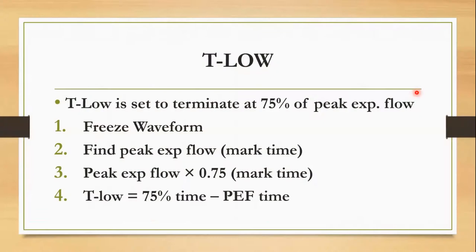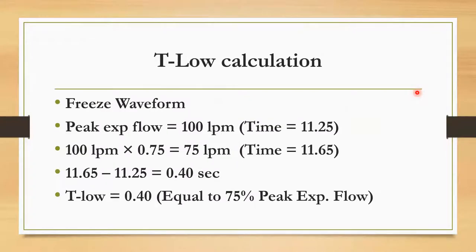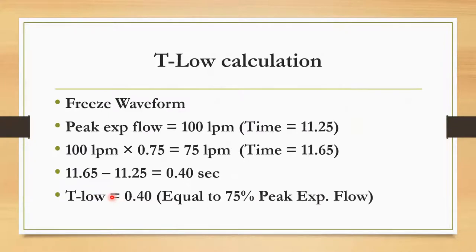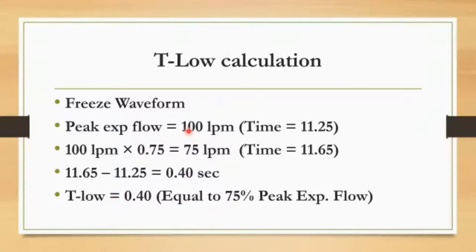The T-low is set to terminate at 75% of peak expiratory flow. Freeze the waveform, find the peak expiratory flow, mark the timestamp, multiply by 0.75, look at that timestamp, and take the difference — that's your T-low. Using 100 L/min as an example: find peak, calculate 75 L/min, identify the timestamp, and the time difference is your T-low setting.